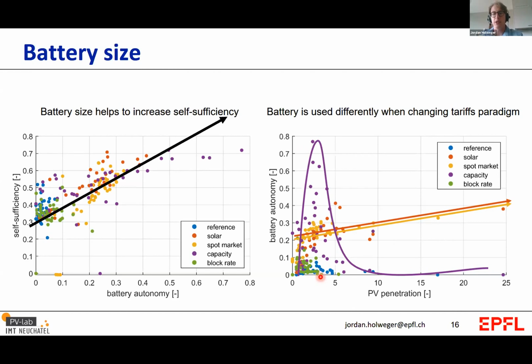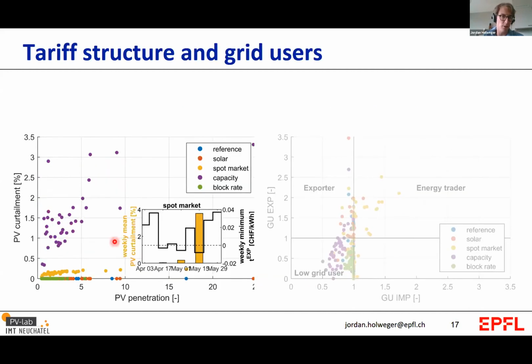a low PV penetration. And this is due to the fact that at low PV penetration, what dominates your maximum power is the import peak power. So you will need the battery to cut this power peak, and you will then need a very big battery. As for high PV penetration, as we will see in a minute, you can use curtailment. You can just curtail your PV generation to reduce your export peak.